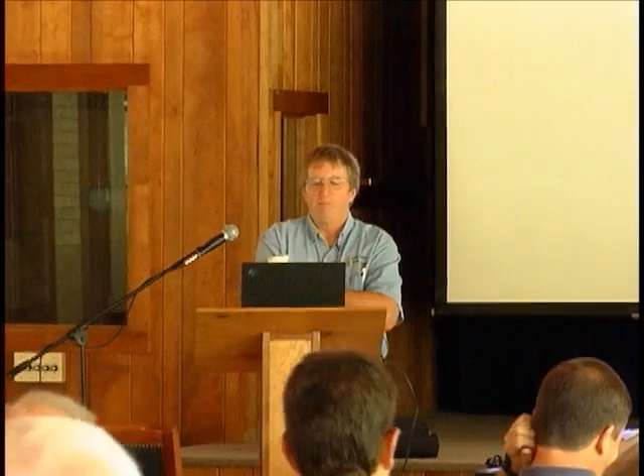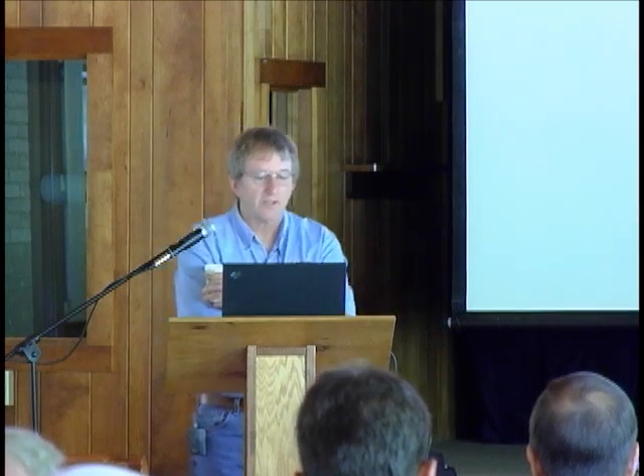But this is my worstest case of an Art Crawford job right here. Boy, this one just almost drove me out of my mind. So again, I think he called because I've got a nuclear background, and this is a high-pressure core injection pump. This is a boiling water reactor, and this is one of the pumps that you never run except maybe once a month to check it out. But in case of an accident, you'd need to have this pump in operation so you don't melt the core down, which is a bad thing.